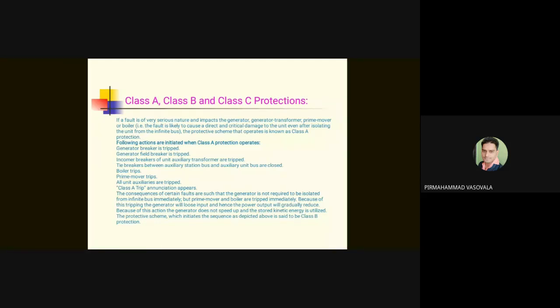Boiler trips. Boiler tripping means the flame that is being fed by the burners, those burners are tripped. No coal will enter the boiler, no air will enter the boiler, so that the flames are extinguished. That is the meaning of tripping of the boiler. Then the prime mover trips, that is, the steam stop valve is closed so that no steam enters the turbine. All unit auxiliaries are tripped, that is, the PA fan motor, FD fan motor, ID fan motor, and the class A trip annunciation appears.